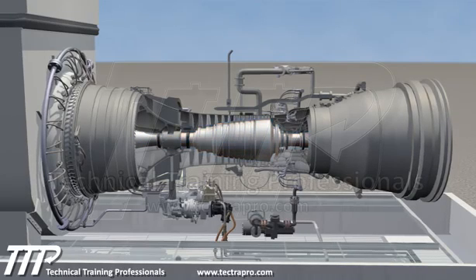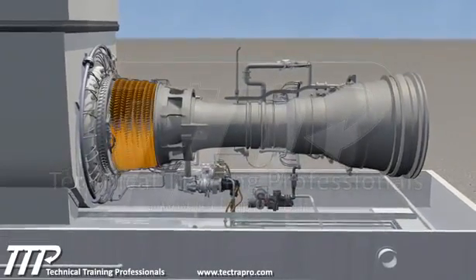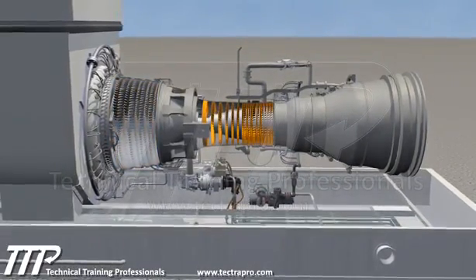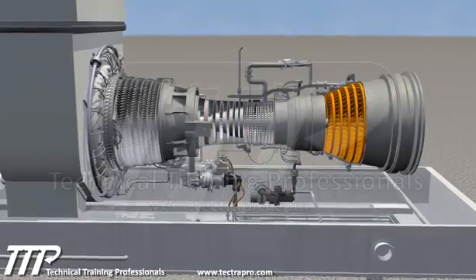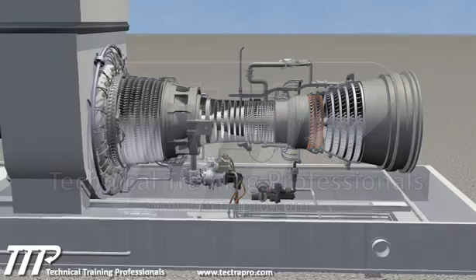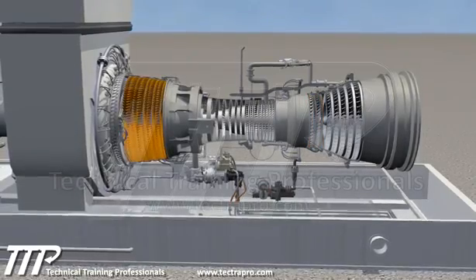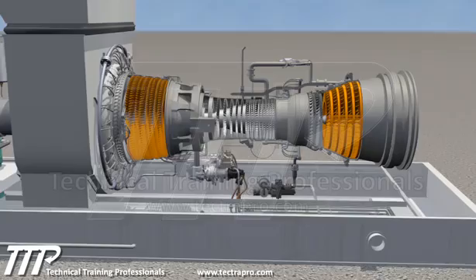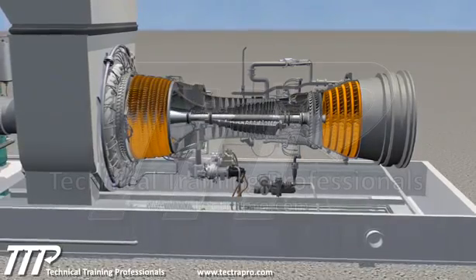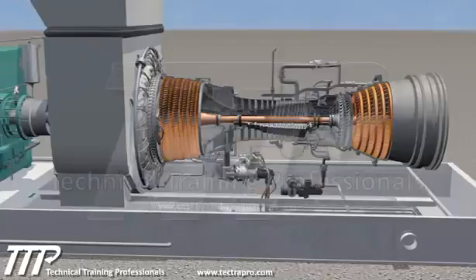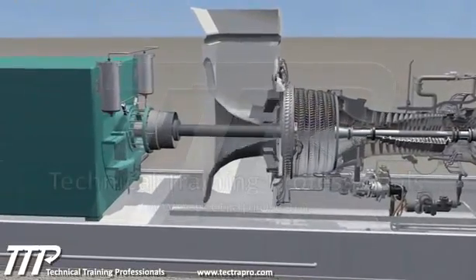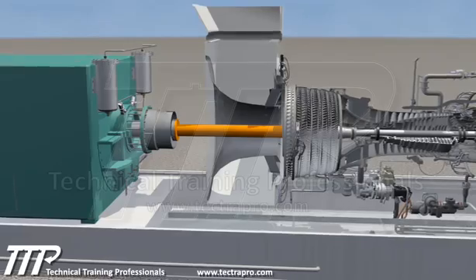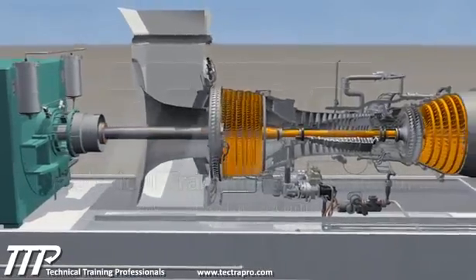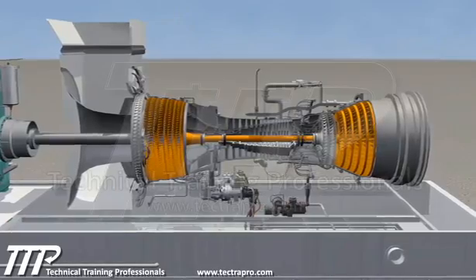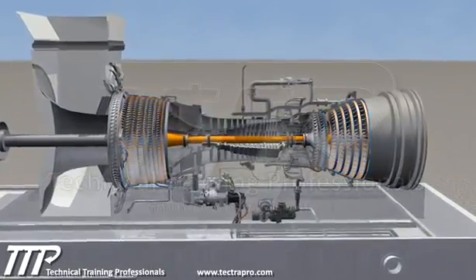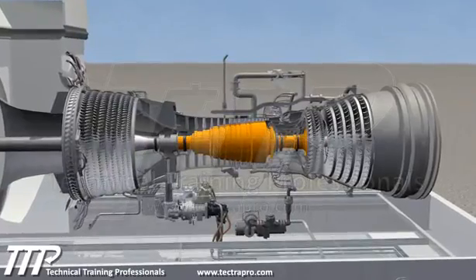There are four sections to the turbine: a low-pressure compressor, high-pressure compressor, low-pressure turbine, and high-pressure turbine. The low-pressure compressor and low-pressure turbine are the outer sections and are connected by the inner rotor. The generator attached to this turbine is coupled at the low-pressure compressor side. The low-pressure system rotates at 3,600 RPM. The low-pressure rotor is located within the high-pressure system rotor.